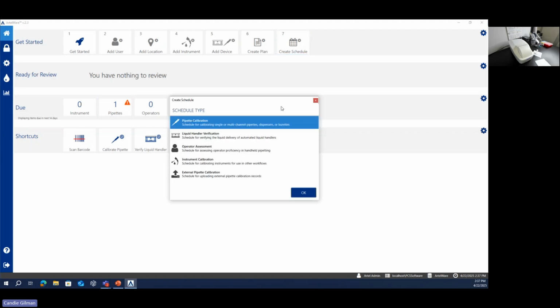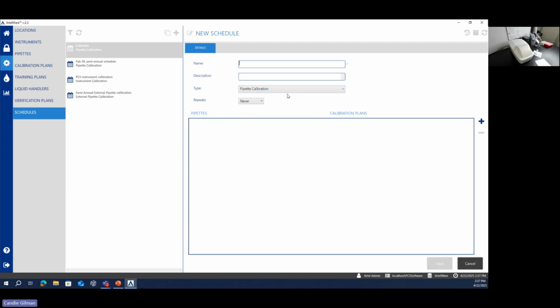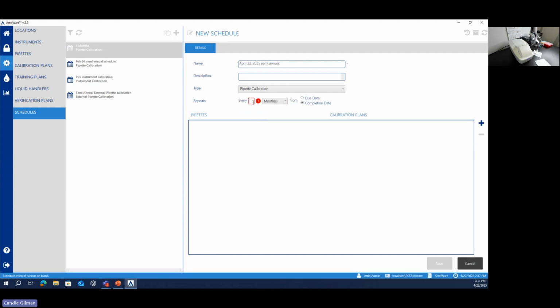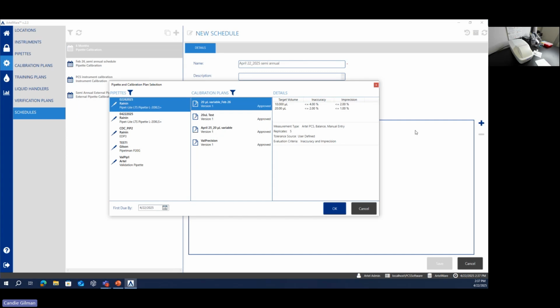So the moment I click on Create Schedule, I have a few options of the types of schedules I want to create. I can create a Pipette Calibration schedule, an operator assessment schedule, etc. But of course, we're dealing with Pipette Calibrations today. So I'm going to call this April 22nd, 2025 semi-annual schedule. And from here, I can select how often this schedule repeats. So it's semi-annual, so I'm going to have this repeat every 6 months from the completion date of when I actually perform the calibration.